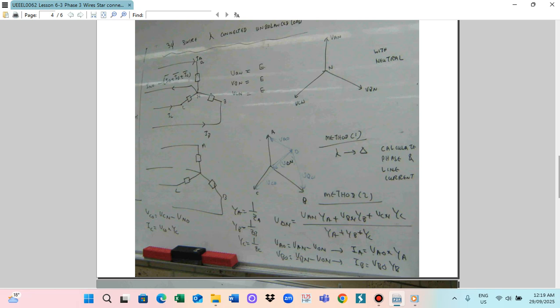So in this case, the voltage will change. So this is the VAO, VBO, and the VCO. The voltage will be changing. So this voltage VNO, because the original star point is changed to the new point, all phase voltages will be changing. Phase voltage changing means that some phase has an over voltage, so that all equipment connected to this over voltage phase can be damaged.